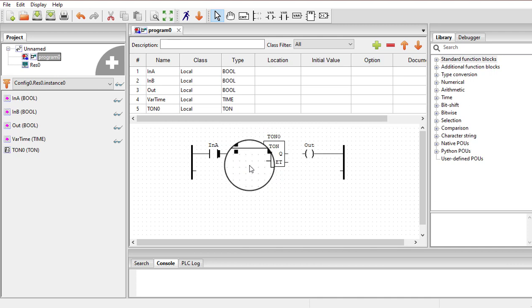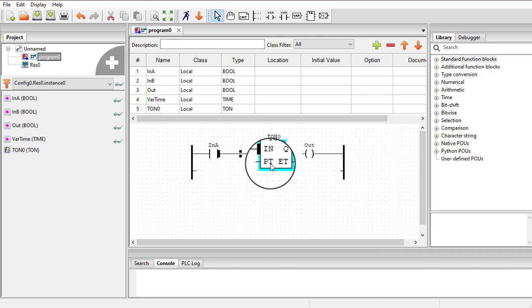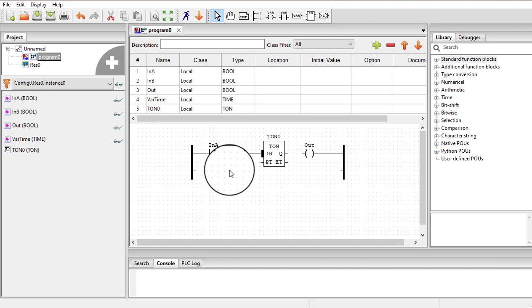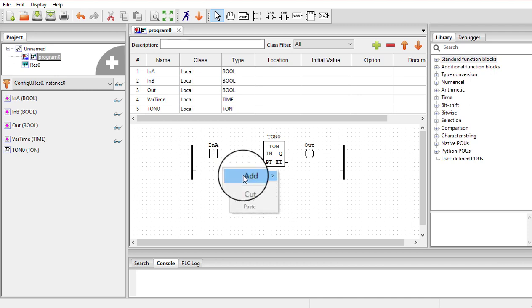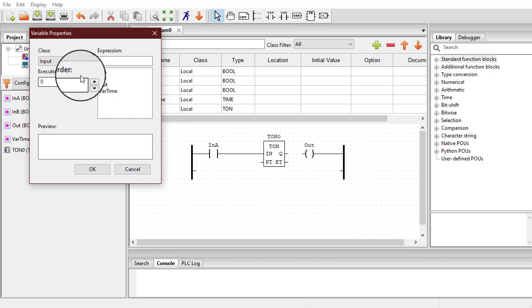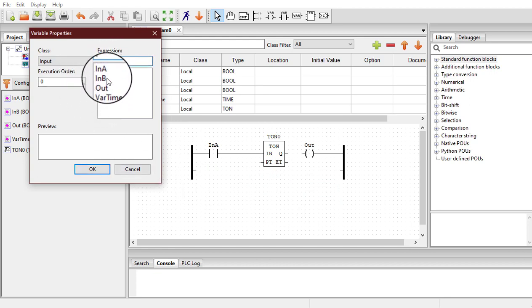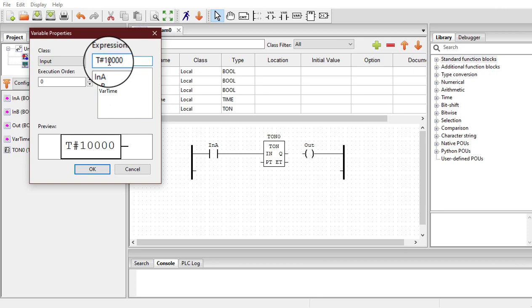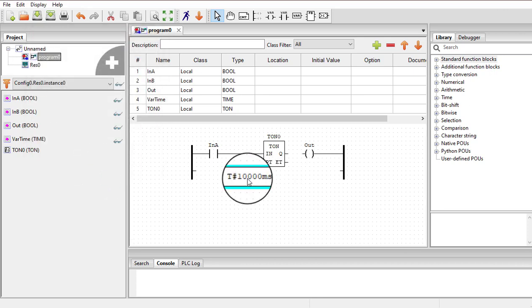For the timer we need a preset value — how much time this timer should time. We provide the preset time at the PT pin. To do this we use an expression from structured text programming. Right-click and add a variable, then write an expression. To insert time, the expression is t# followed by the time in milliseconds. For 10 seconds, enter 10000 milliseconds. Click OK and attach this block to the PT terminal.